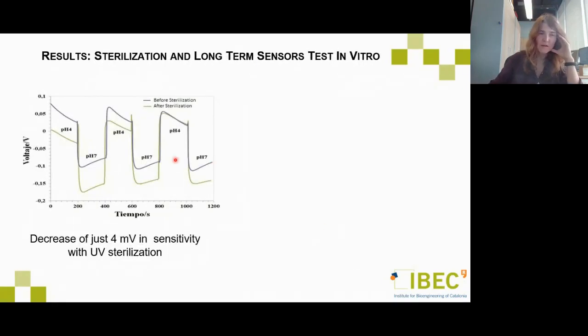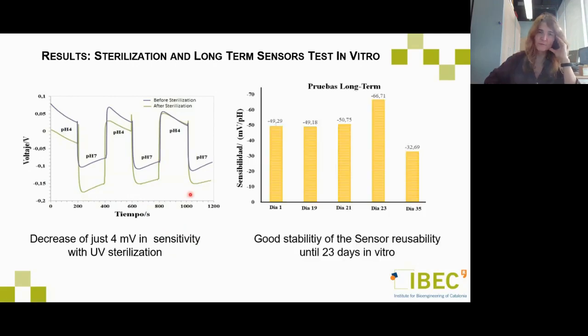Also, we made some tests of the sterilization of this kind of wire electrodes, because basically we need to introduce them inside the body, so we need to be sure that we are able to sterilize these sensors and that they are not highly affected by this sterilization. The sterilization that works best for us was the UV, ultraviolet, which just reduces the response of these sensors by 4 millivolts. Here you can see also a long-term analysis of the pH sensor.